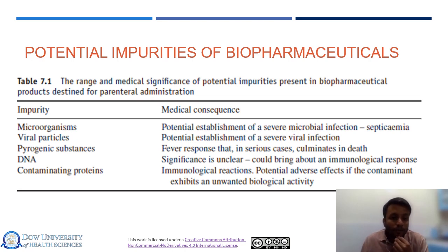Then there are pyrogenic substances. They can cause a fever response in the patient, and can also lead in certain cases to death. These usually come into the product from the water that is being used, or if the glassware is not washed properly or properly depyrogenized. So these are the potential sources that can introduce pyrogenic substances into the product.